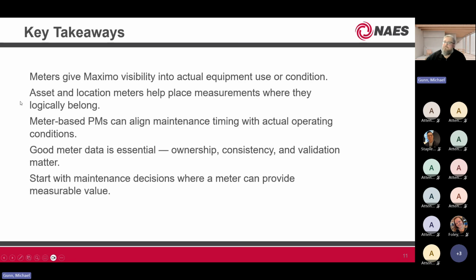I'm not a fan of repeating things in PowerPoints, but it happens - meters give Maximo and you visibility into actual equipment use or condition, and using asset and location meters helps you place those measurements where they actually belong. A data analyst years down the road can sort through readings, but it's very hard if they're not directly tied to assets. If I can go to a specific boiler feed pump and look at every meter associated with it over the past 10 years, that helps in the long run to analyze.